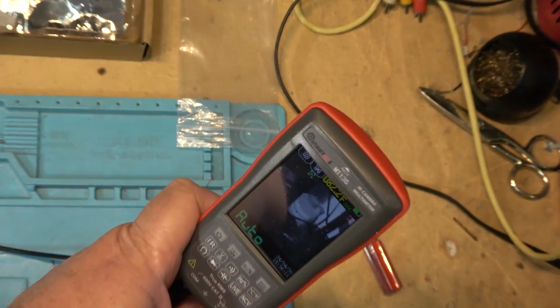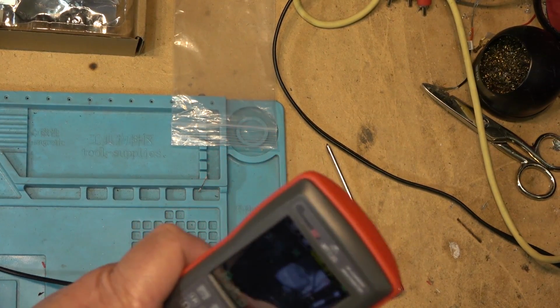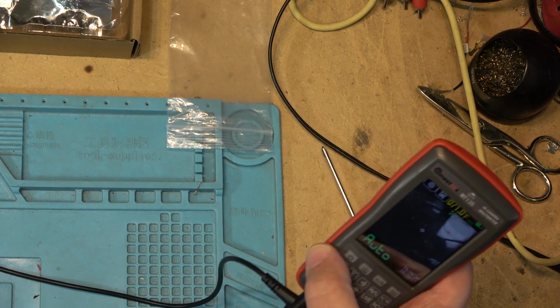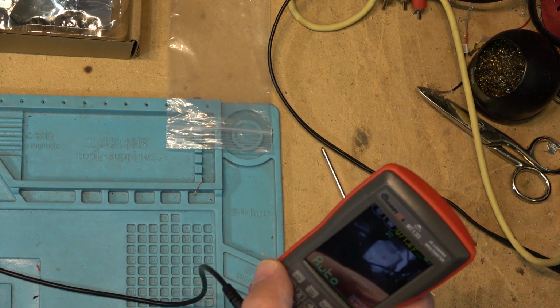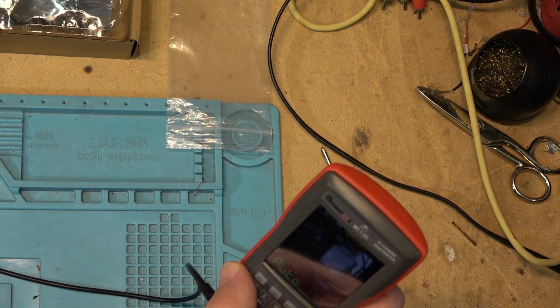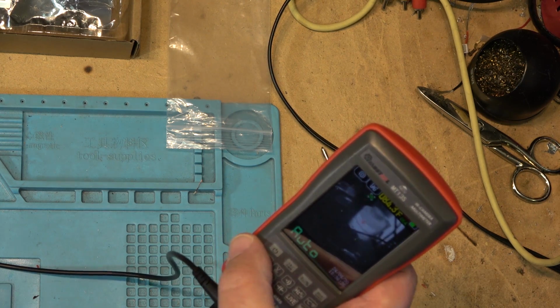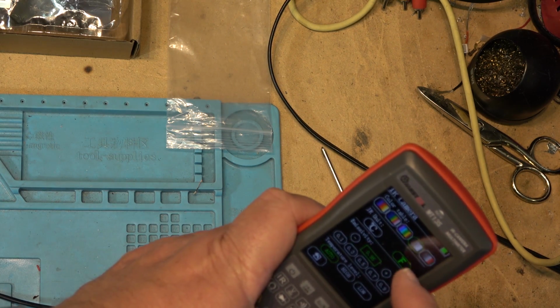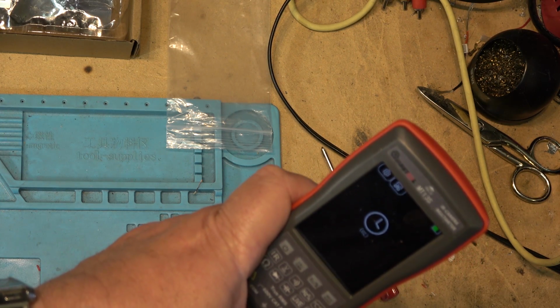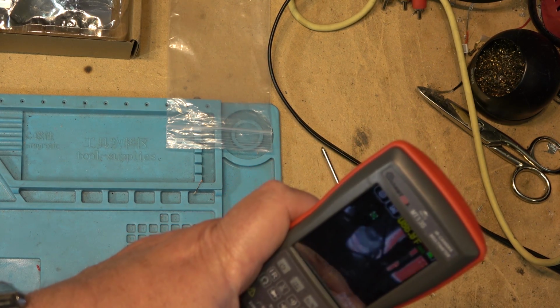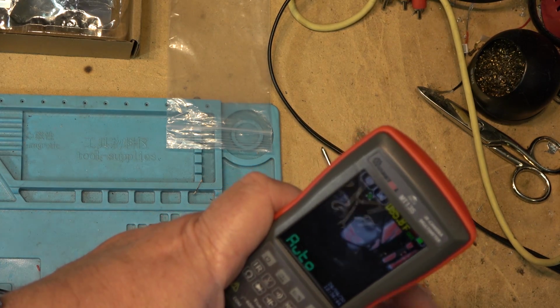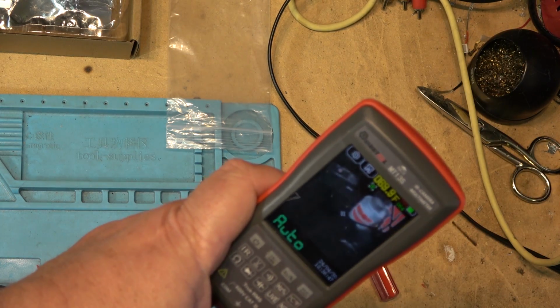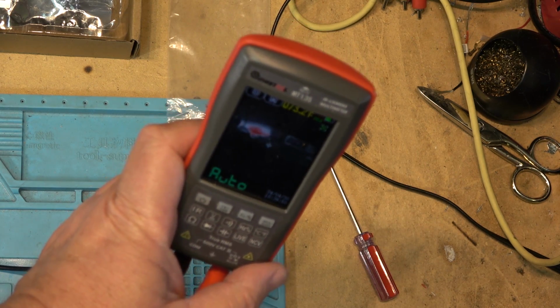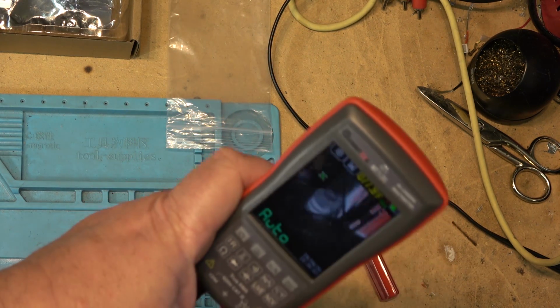So right here you can see the transformer. It's glowing away. Many times it's a little easier to tell something that's hot if it's white as opposed to other surrounding colder areas. But you've got the option. That's one. The other ones are, you can have this one, which is white hot, or red hot, I think it is. It's black and white, but the hottest areas are shown in red, you see. So this one here, it's a black and white image, but the hot spots are shown in red. So that'll draw your attention to something that's hotter than anything else on the screen.